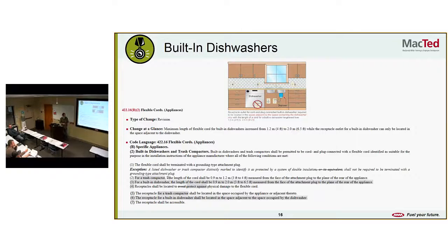Okay, that makes sense. What else did they add here? For a trash compactor, the length of the cord shall be 3 to 4 feet, measured from the face of the attachment plug to the plane of the rear of the appliance. For a built-in dishwasher, the length of the cord shall be 3 to 6.5 feet, measured from the face of the attachment plug to the plane of the rear of the appliance. Receptacle for a built-in dishwasher shall be located in a space adjacent to the space occupied by the dishwasher. Receptacle shall be accessible. So, makes sense.